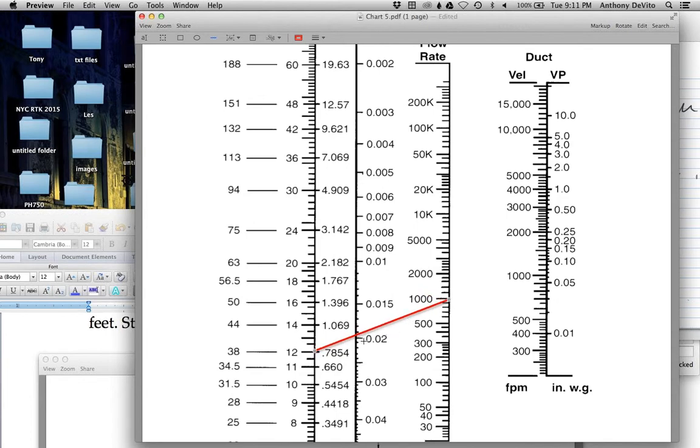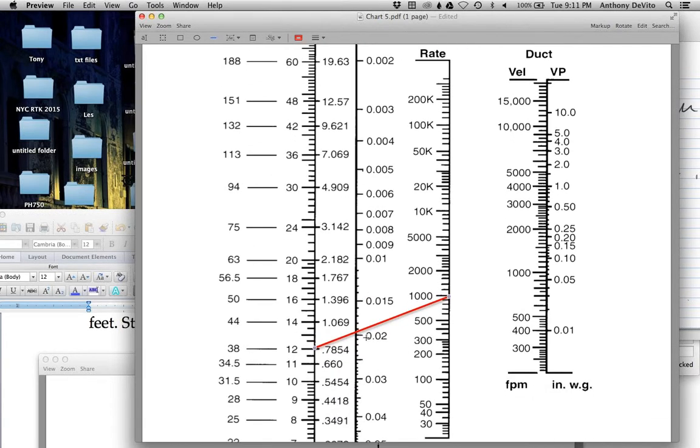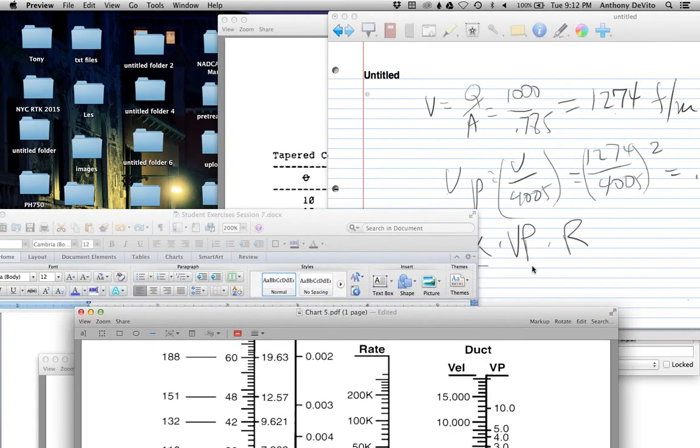And what do you get for the K for the friction loss due to ductwork? K is equal to, well, this is 0.02, this is 0.015, so it's 0.016, 0.017, 0.018, 0.019, it looks like. You guys happy with that? Is that okay? Right? 0.019. We all agree, right? Okay, so 0.019 is what our K factor is going to be.